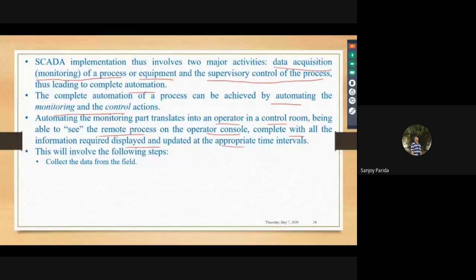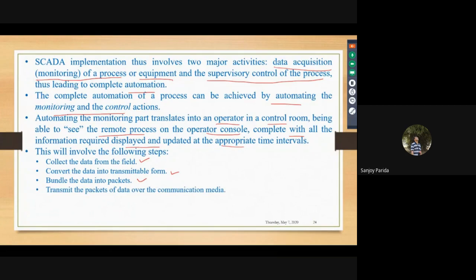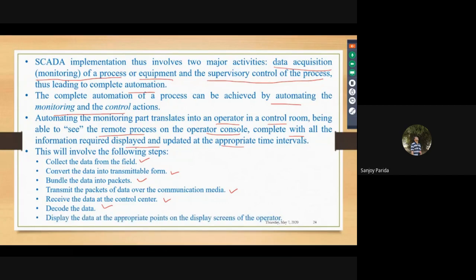The first step is to collect the data from the field, then convert the data into transmittable form, since it has to be sent through some communication channel. Then bundle the data into packets, transmit the packets over the communication media, receive the data at the control center, decode the data, and finally display it at the appropriate points on the display screen for the operator.